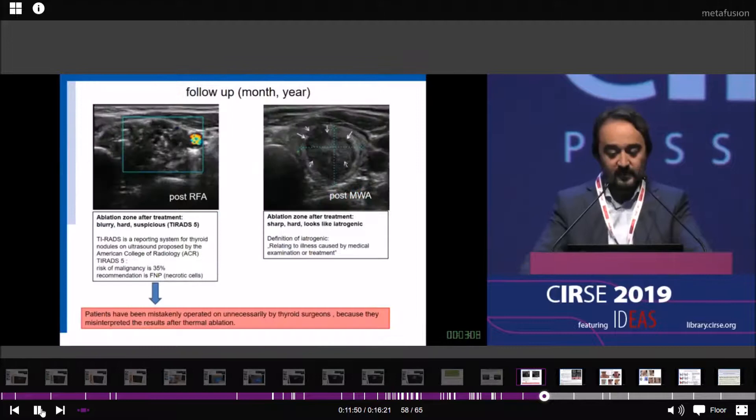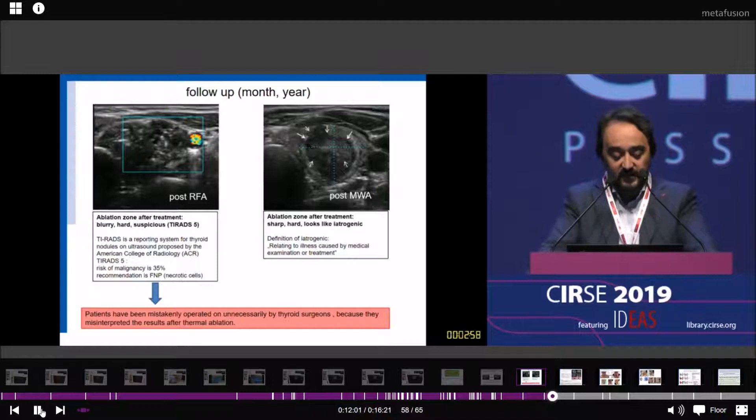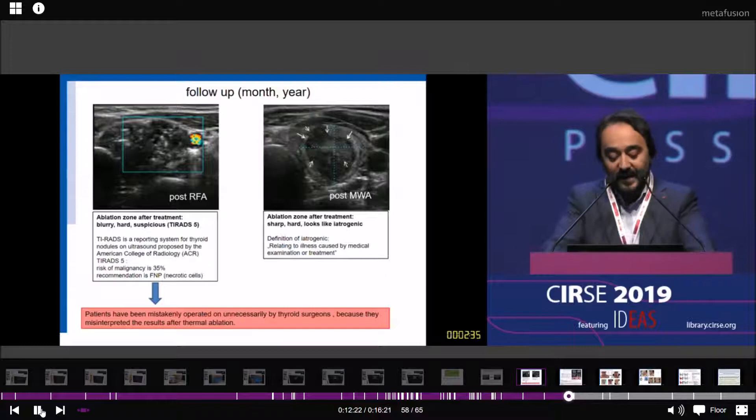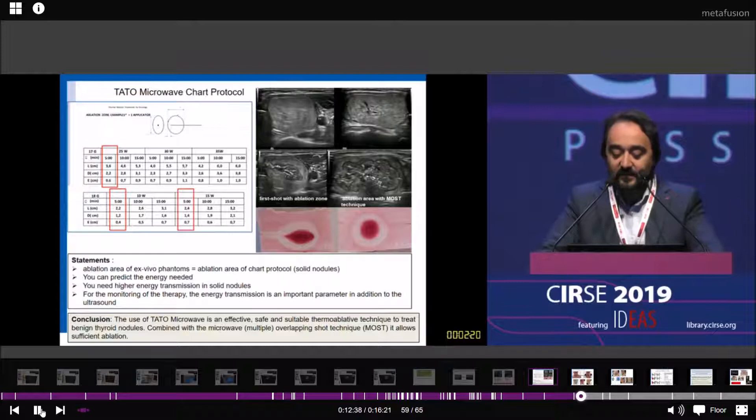In follow-up imaging, the ablation zone of RFA is very blurry, hard, and suspicious. Using the TIRADS reporting system, the risk for malignancy is up to 35%. With microwave, you have a very sharp ablation area. We know that some patients have been mistakenly operated on by thyroid surgeons due to this. Using the TATO microwave chart protocol for solid nodules, we see the same ablated area in-vivo and ex-vivo, so you can predict the energy needed. Energy transmission is an important monitoring parameter in addition to ultrasound.